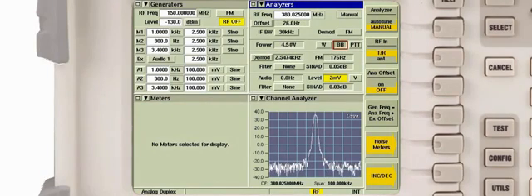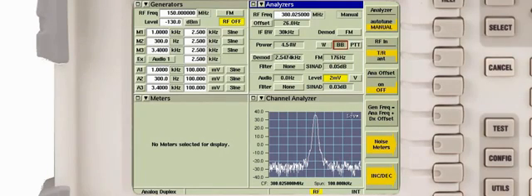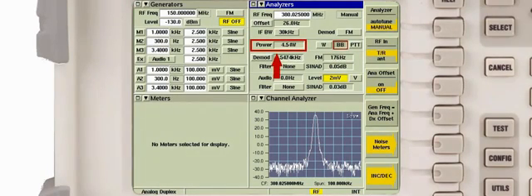The radio is transmitting a UHF band signal into the instrument through the TR connector. The broadband power meter indicates that the signal power is 4.54 watts.